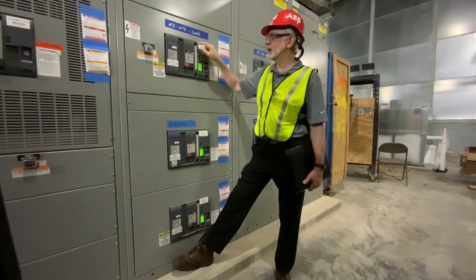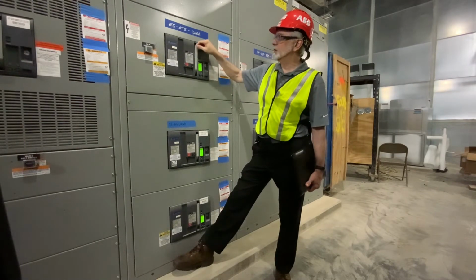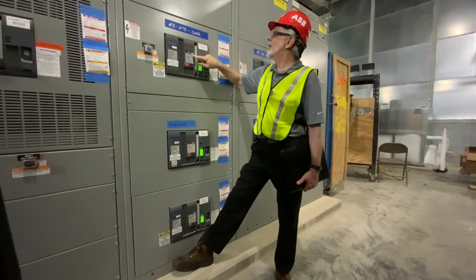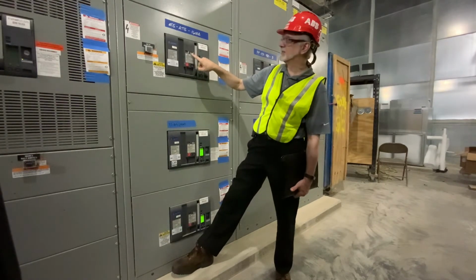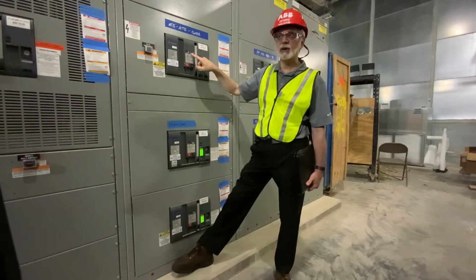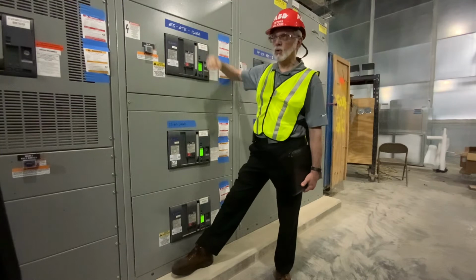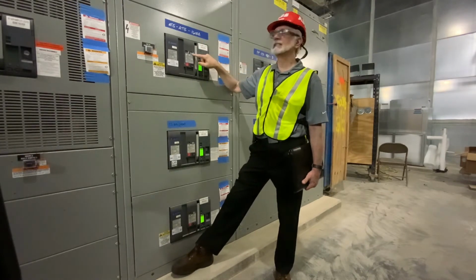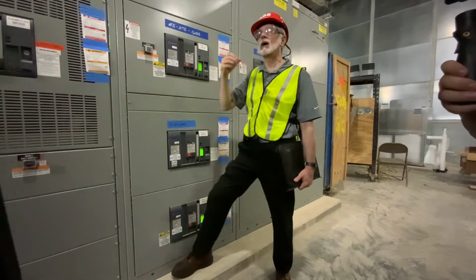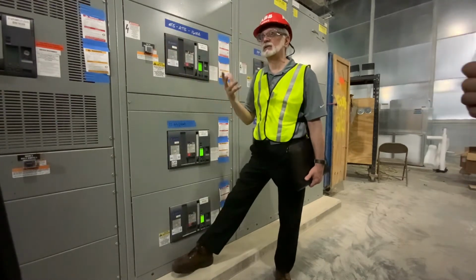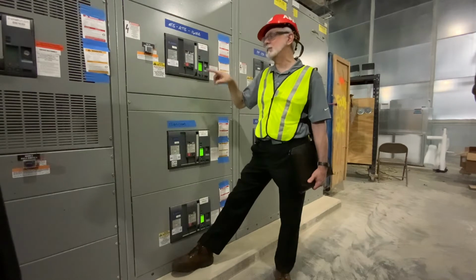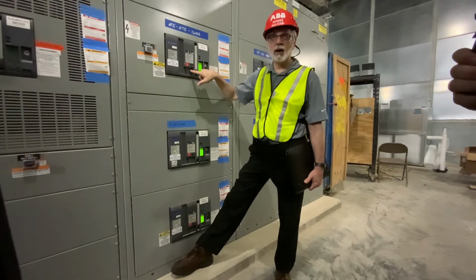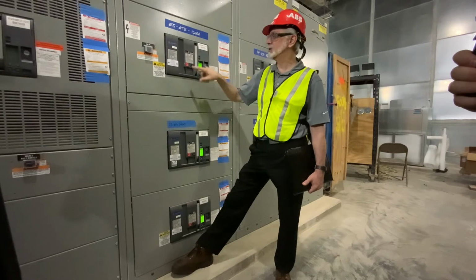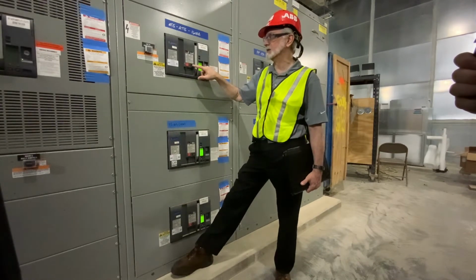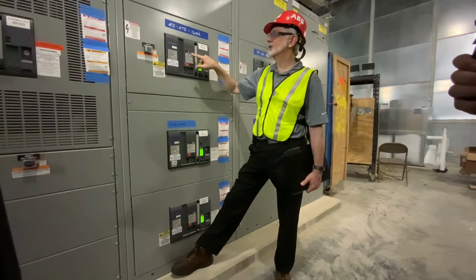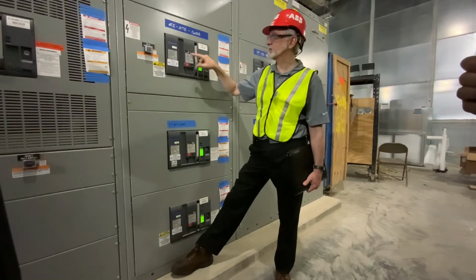So this is what we call the stored energy breaker. What you do is you use this handle to crank it down, and right now it says discharge, so this particular breaker, the springs are discharged. So what you would do is you would crank the handle down until it says charge, okay? You'll also hear a sound, like the springs are then charged, okay? That would give you the ability to then close the breaker if you wanted to at that time. So you can open and close the breaker through these push buttons, and you can also see whether the springs are charged or discharged through these mechanical flags.